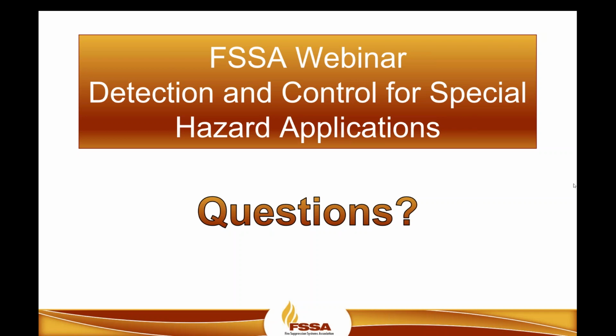Great. Okay, next they're asking, what are the... Well, we'd follow NFPA 72, but as an industry standard, we typically use 250 square foot unless otherwise specified in a releasing system scenario. 250 square foot ceiling subfloor above, unless, again, you have an AHJ like FM Global, that would require you to go down to 125 foot spacing per detector.